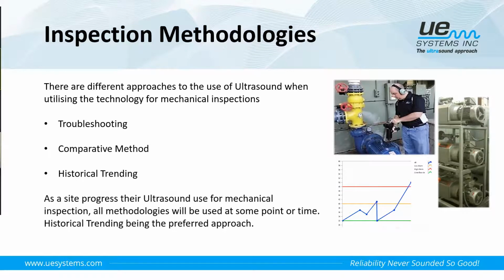So we have the troubleshooting method, we have comparative inspections, and then we have historical trending. And as a site progresses through the use of ultrasound from the start, they will implement all of these types of approaches at some point or another, eventually getting to a point where they'll have historical trending being used, which is normally the preferred approach for us to understand what's going on.